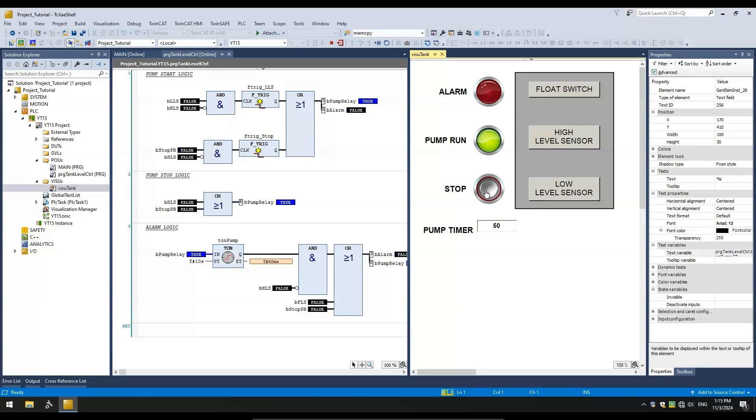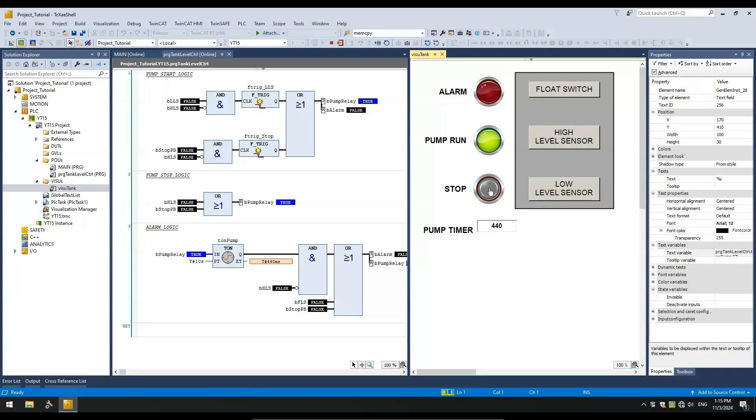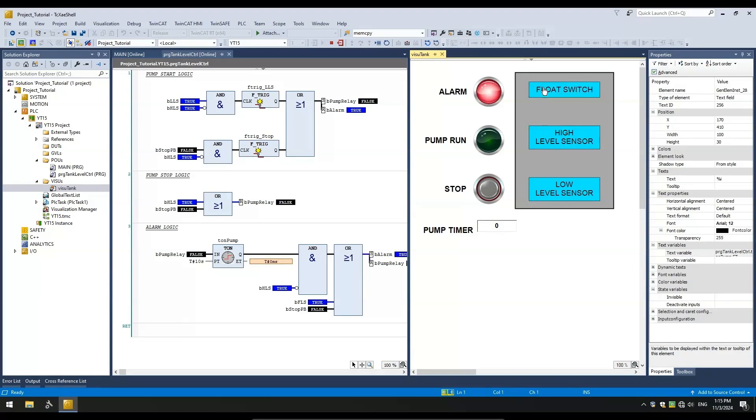Toggling the start button clears the alarm and starts the pump. The HLS stops the pump as before and the LLS starts the pump. Pressing the stop button also stops the pump and triggers the alarm. Just what we wanted. Now, pretend that the pump is unable to stop and continues filling the tank which will trigger the float switch. This causes an alarm. Good.